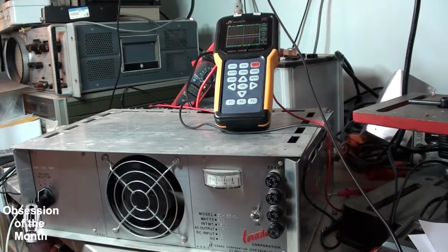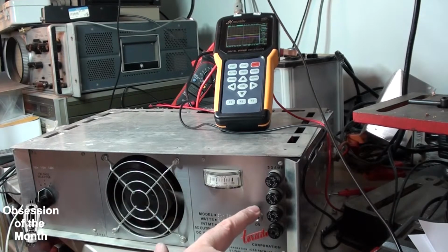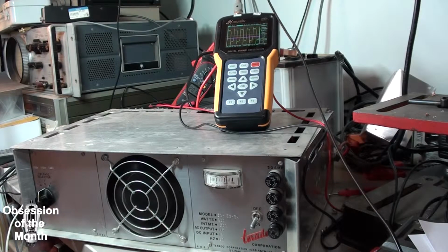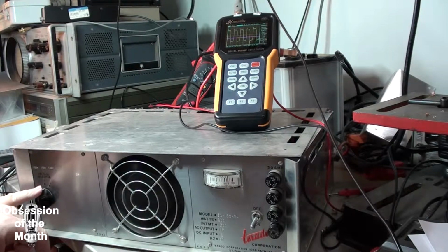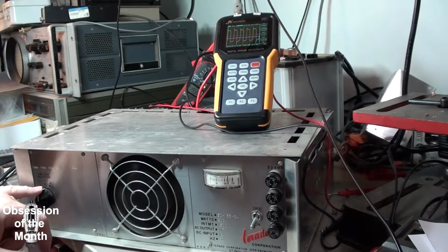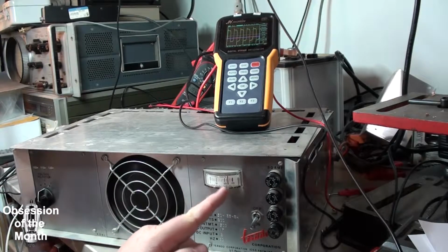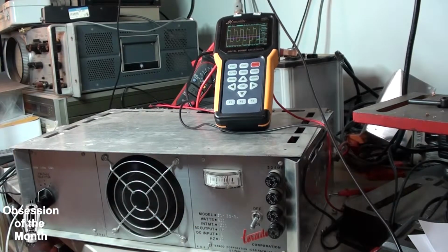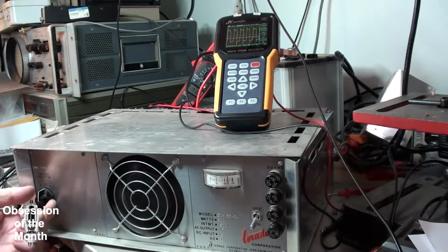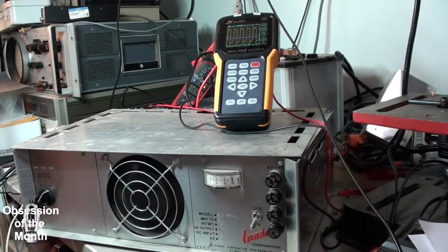So I'm going to turn it on. You'll notice the selector is set to 115 volts, and that setting reads 120. I had to mess with it to try to calibrate it — it's only really accurate at 105 volts. Every other setting is not correct. Now it's on 125 volts.